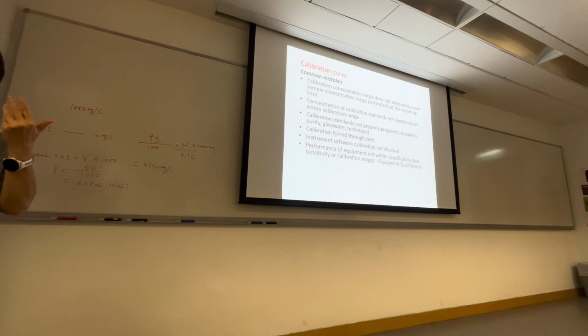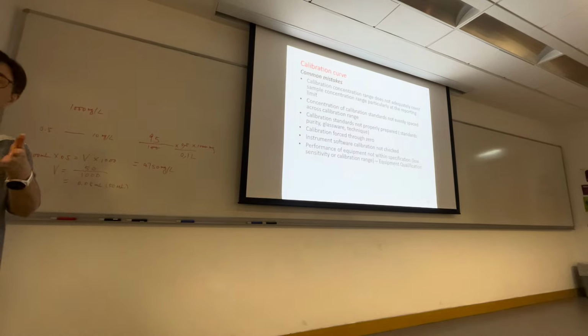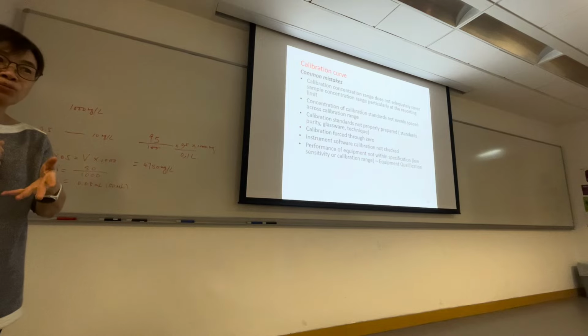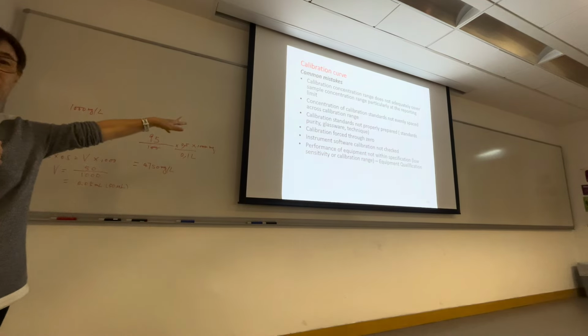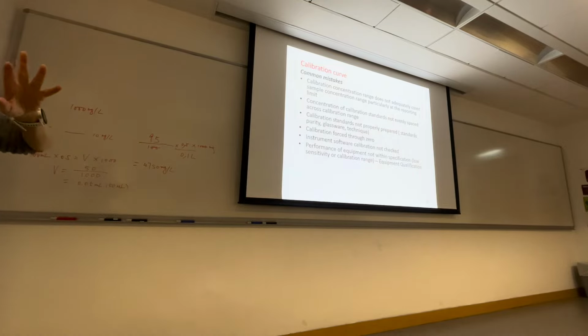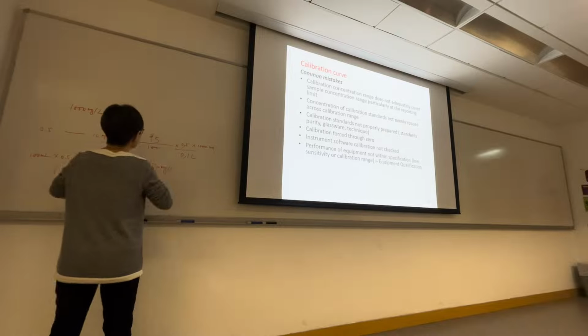Still remember when we talked about acid, for different types of acid, the amount of impurity can range from ppt to ppb and then to ppm. So it all depends on what calibration blank you use. It may contribute a background signal. So for some laboratories, they just neglect that point and force through 0. What is the meaning of forcing through 0?